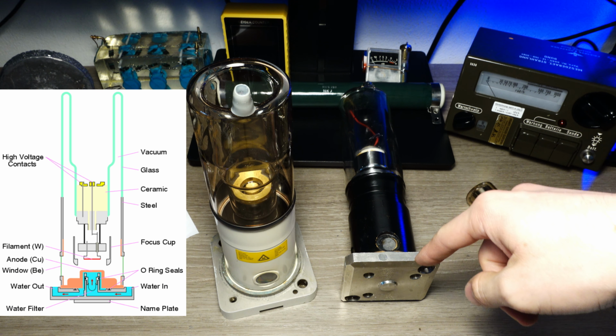This means that the X-ray emitted have an energy spectrum that is a bell, with the peak of the energy of the X-ray emitted at around 1/3 of the voltage applied to the tube.